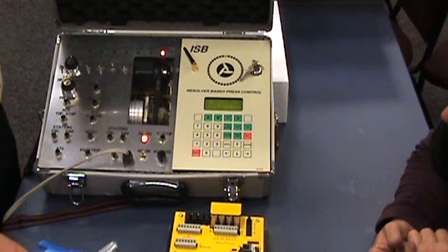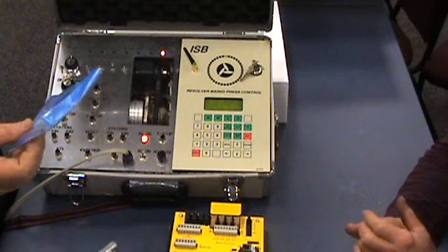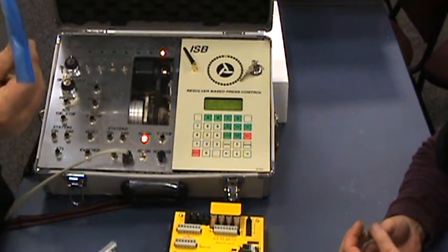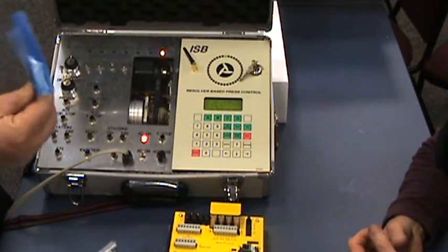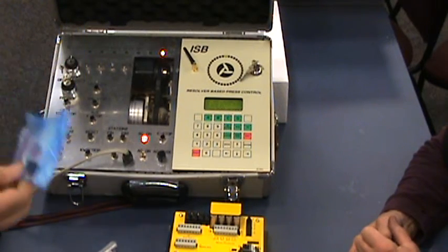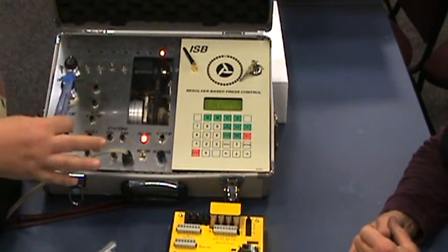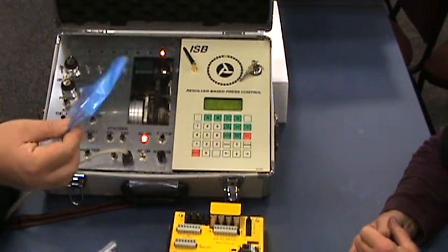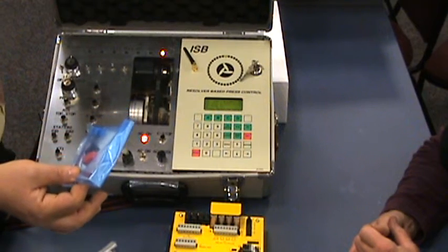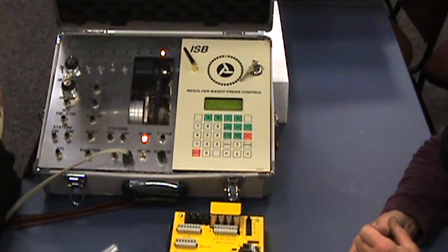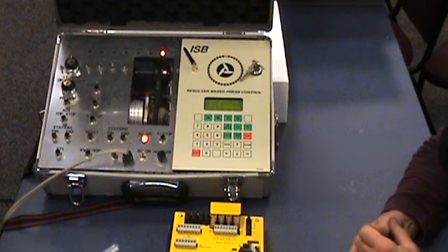But these relays that are in this bag, I go into some maintenance departments and find they've installed a dozen of these and there's a dozen of these sitting in the guy's toolbox. And then I have to have the lecture after the fact that they've already chewed up relays and this is why I started this presentation. The first concern is always the proper installation of the product. Be neat, get your wires, make sure you have earth grounds coming in here correctly, use your suppressor devices, be proactive instead of reactive, and it's going to save you a lot of machine downtime.